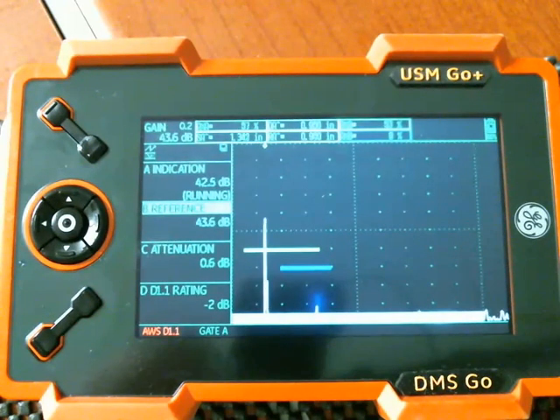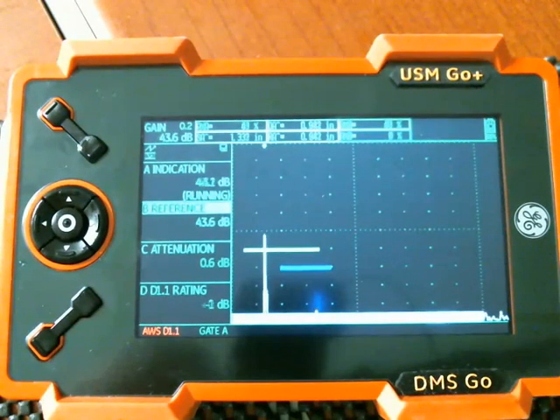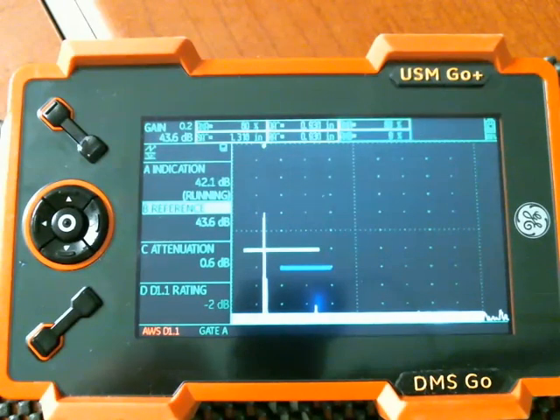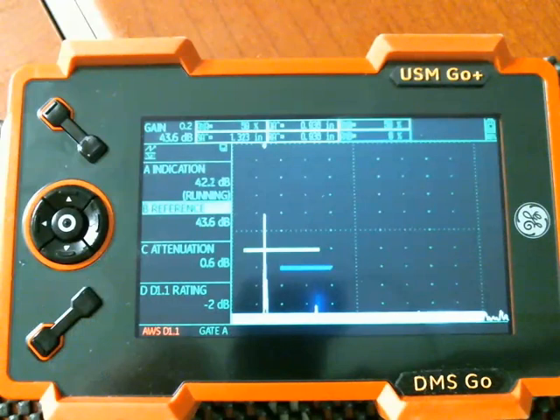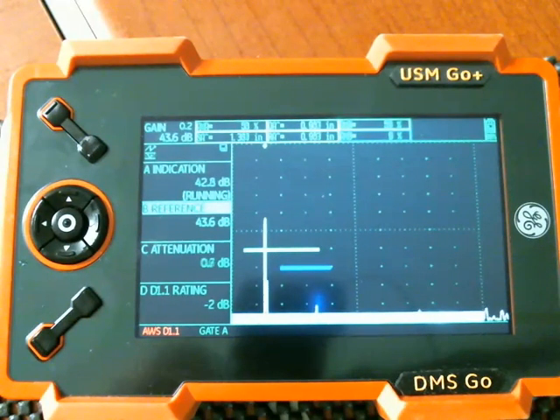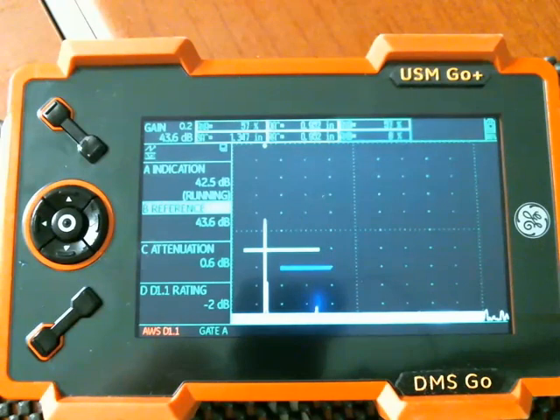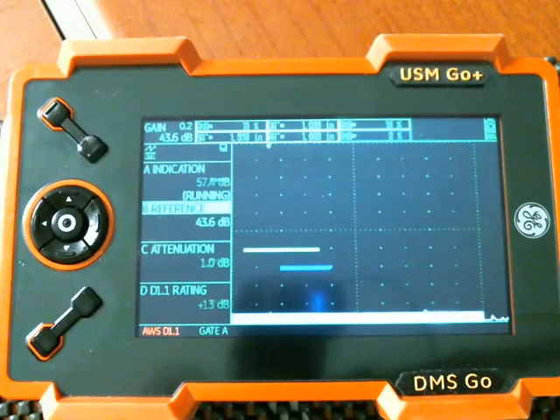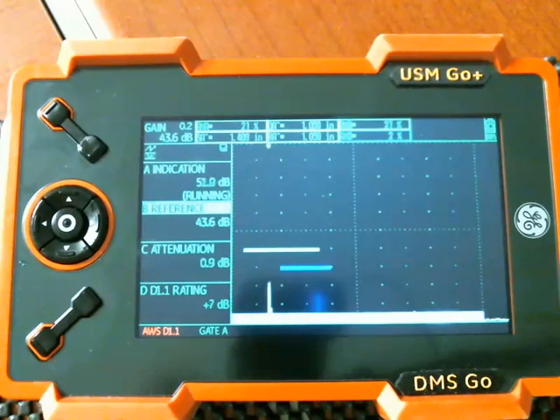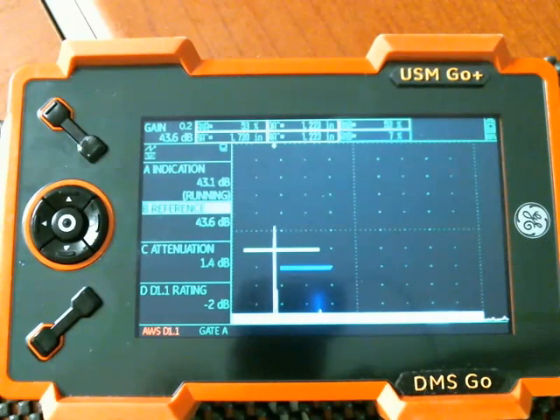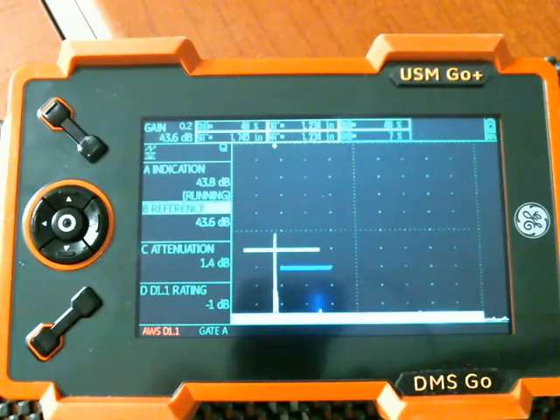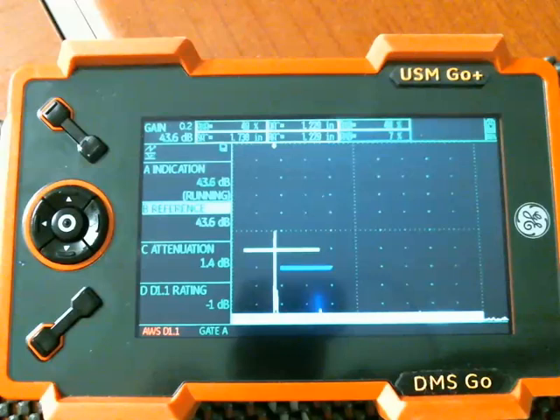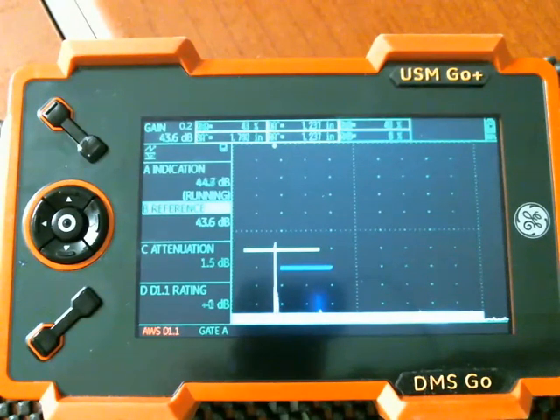So if I go out to a deeper hole, see I actually can peak up a little more sensitivity on that. So it gives me some attenuation on the C factor to account for the greater depth. And it tells me that that hole's actually a little bit bigger or more into natural focus because it's coming up with greater sensitivity even though it's deeper. Slide out to yet a deeper hole. And you can see how the calculator factors in the greater depth on the C factor and gives me the total calculation.